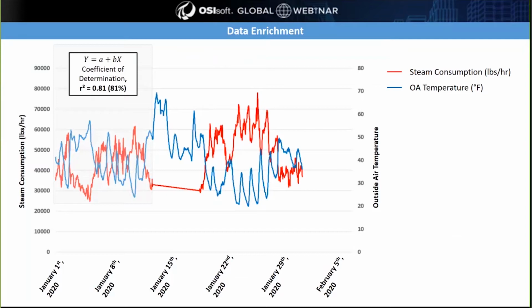In the call-out box here, you'll see I've got the standard form of a regression equation listed, as well as the coefficient of determination, or R squared value. The R squared value, if you're not familiar, is a way to quantify the level of correlation between two variables. In this case, it's saying 81% of the variation in steam consumption is caused by changing temperature. That's a pretty strong correlation, one we can use to estimate the missing steam consumption because we continue to receive temperature data from the National Weather Service.